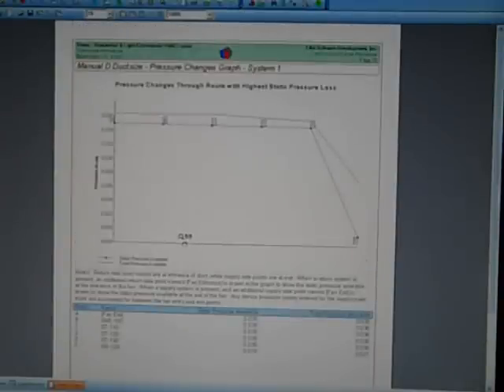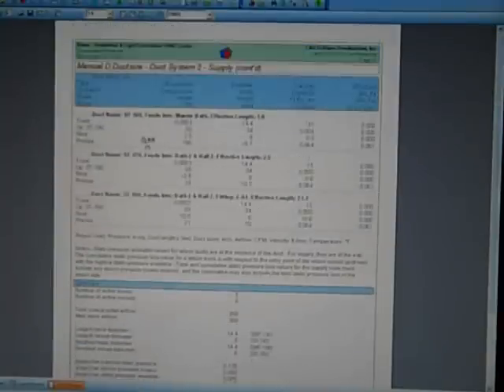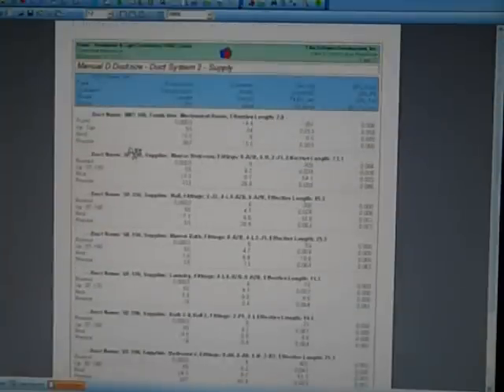I'll stop there for a second. You get a glance at those. You notice the available static pressure on these ducted mini splits is next to nothing. You really got to be careful when you're sizing ductwork for that, and just really err on the side of bigger, because they just have no fan power. They're really intended to be just piped right through the wall without any real trunk or runs on them.